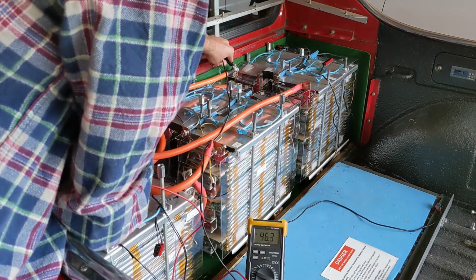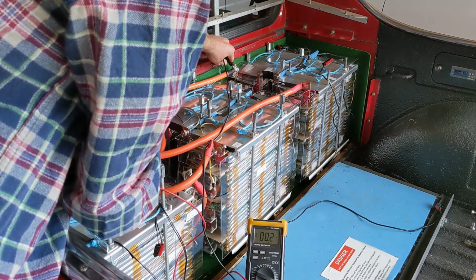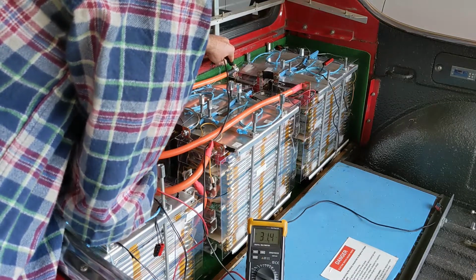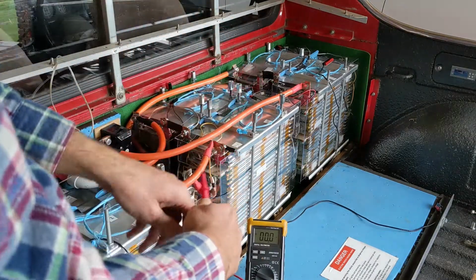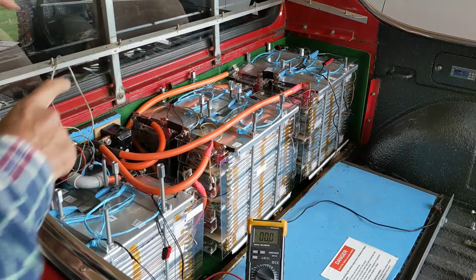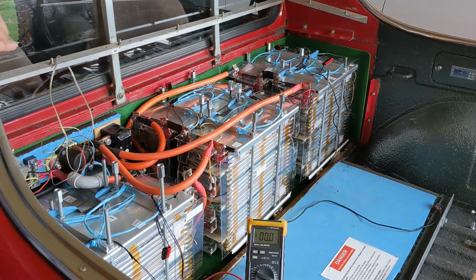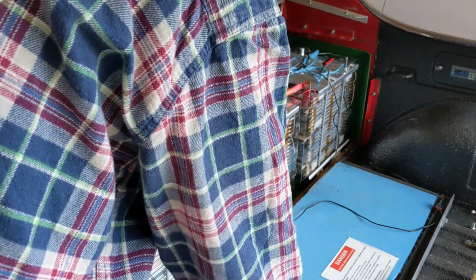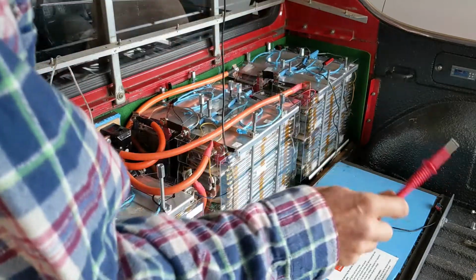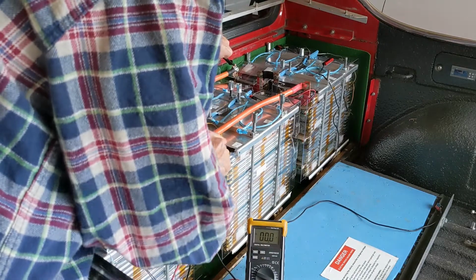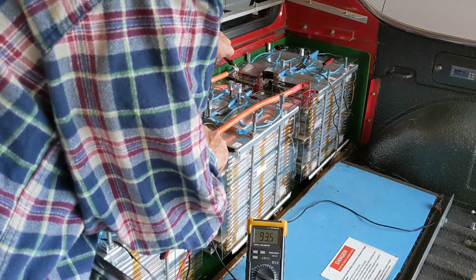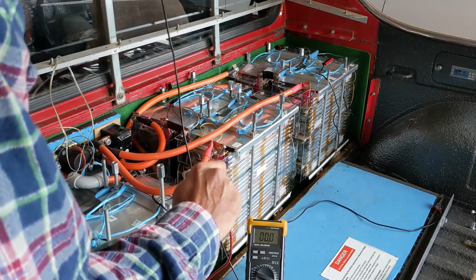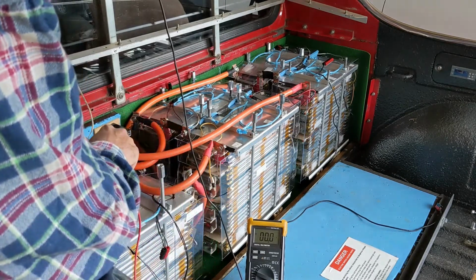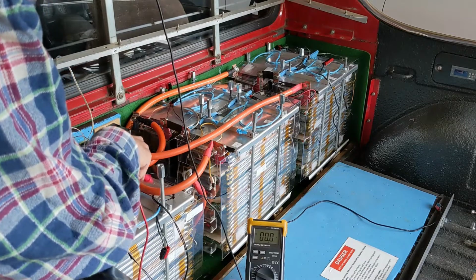So that goes up to the isolation switch and then no further. So when I do the isolation switch, that should bring in the next section. Isolation switch is now not isolating. So go from there to there, 93 volts, don't touch that. And the next one in line is through the mid-pack contactor to there.